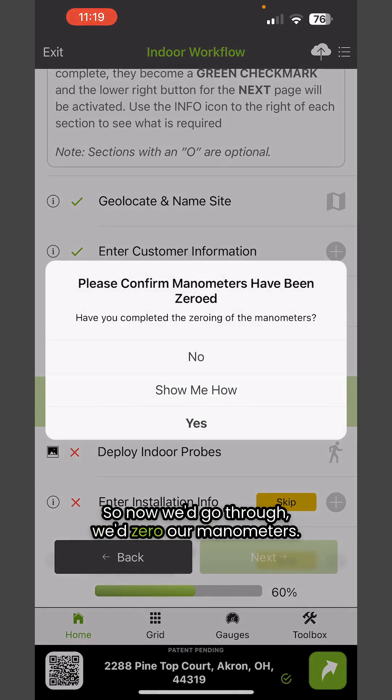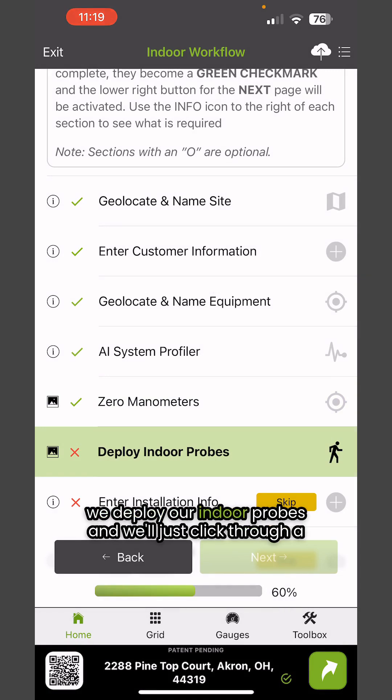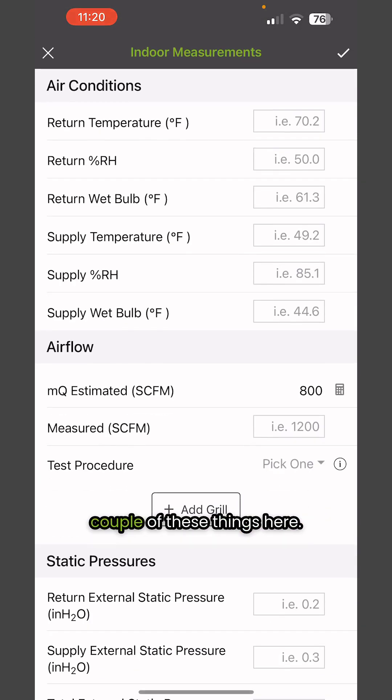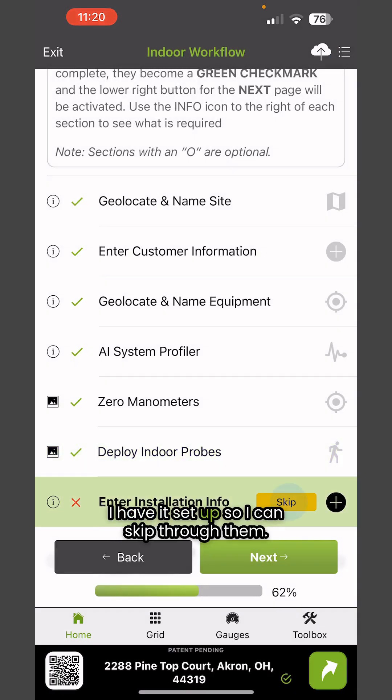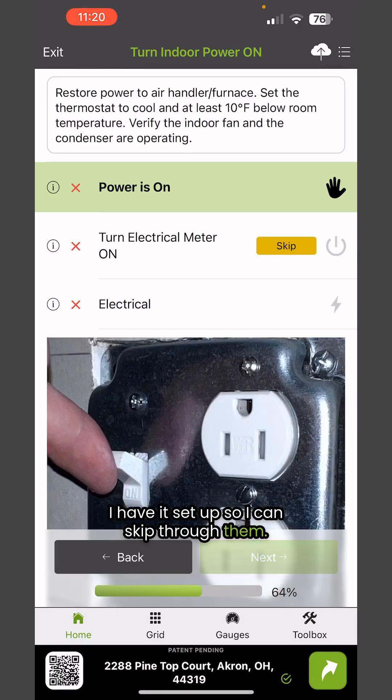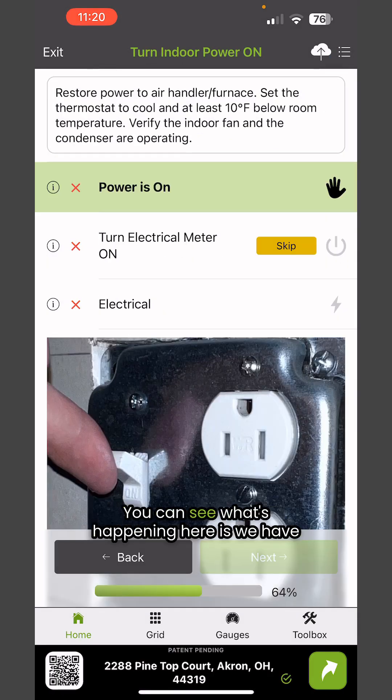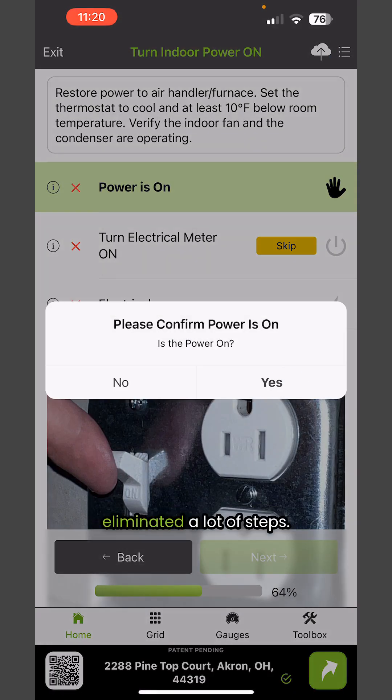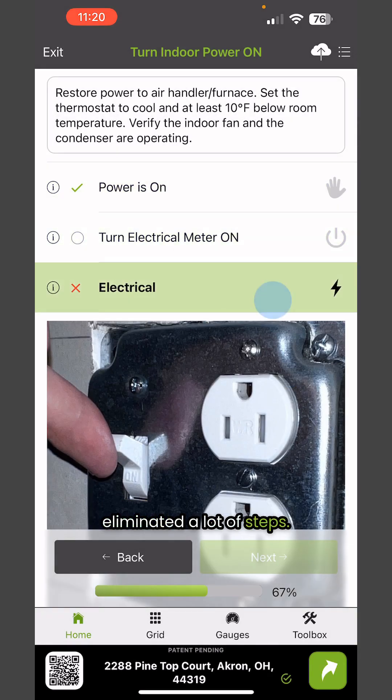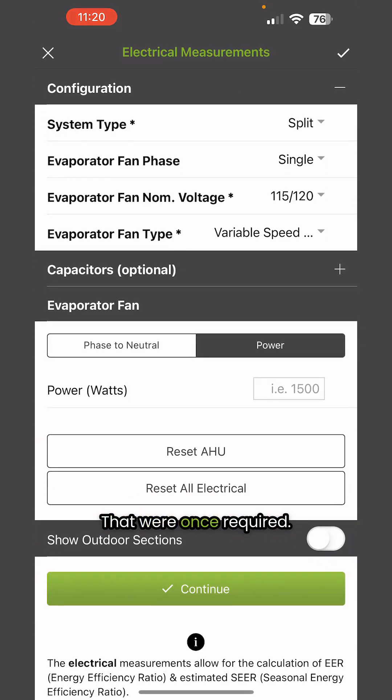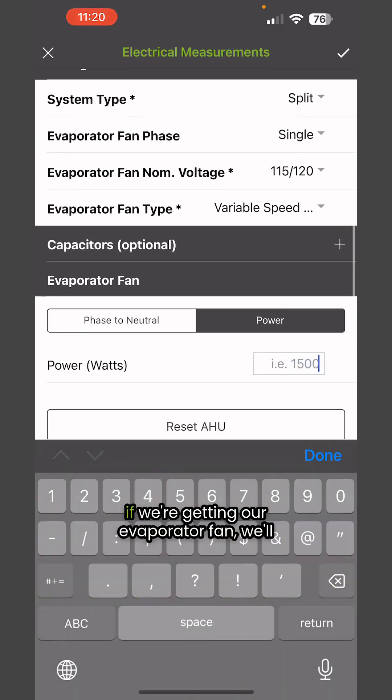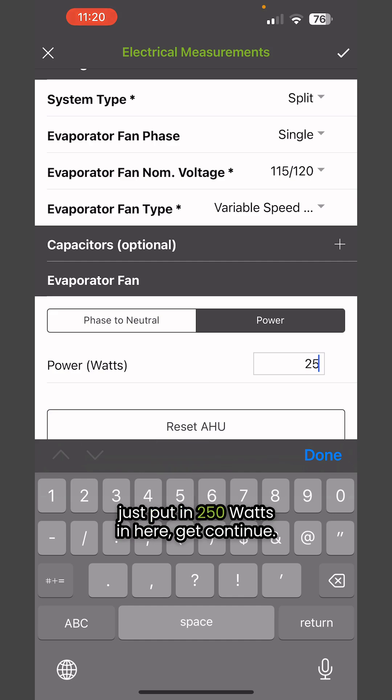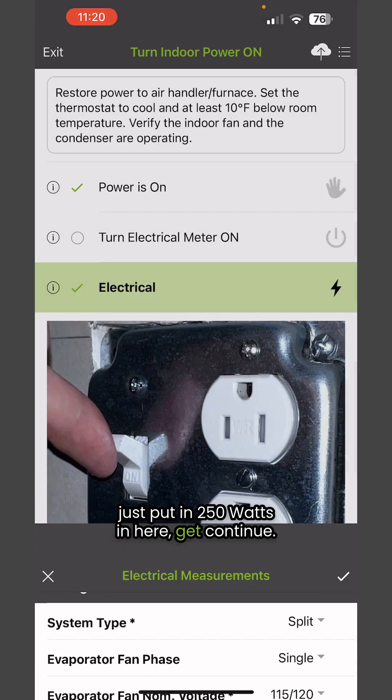Now we go through and zero our manometers, deploy our indoor probes, and we'll click through a couple of these things. I have it set up so I can skip through them. Then we turn the power on. You can see what's happening here is we've eliminated a lot of steps that were once required. If we're getting our evaporator fan, we'll just put in 250 watts. Hit continue.